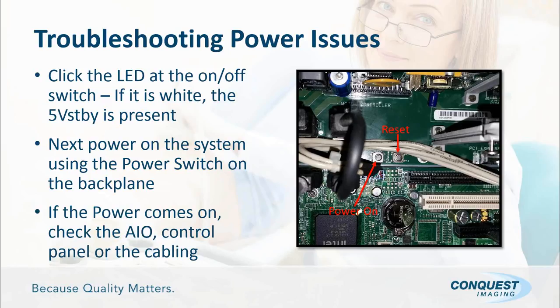So let's start with the power issues. Let's say you step in front of your system and it's running, or not, the white light's present, and you go to press the button, but nothing happens. The system doesn't power on. So we're going to talk about a series of steps to isolate the power problem, or the problem that's not allowing it to come on. If the power does come on, then in all likelihood you have a problem with your AIO, which is your audio input-output module, your control panel, or the cabling.